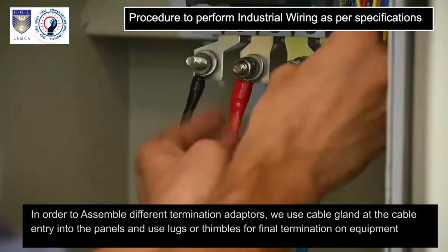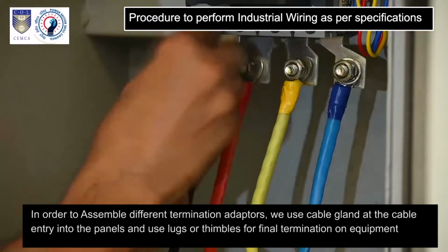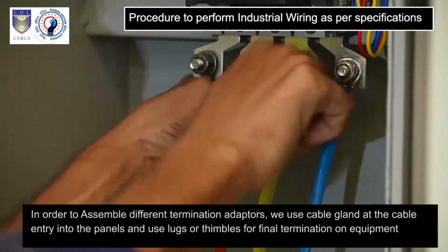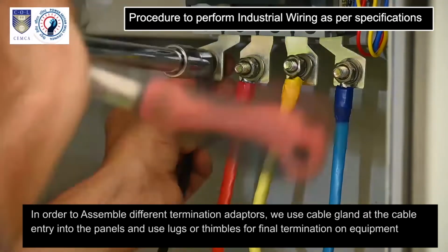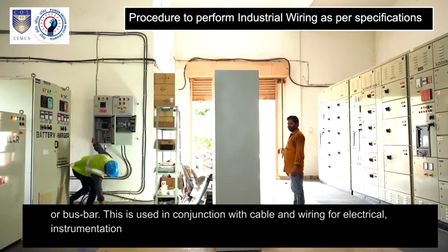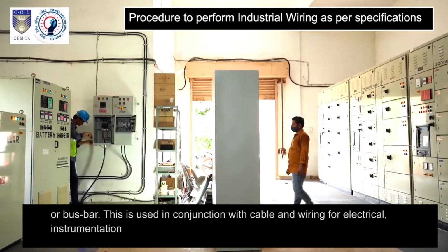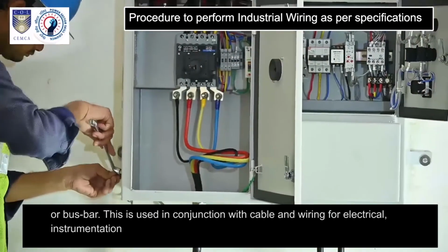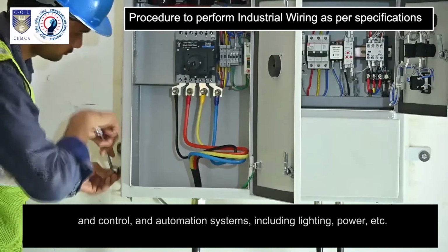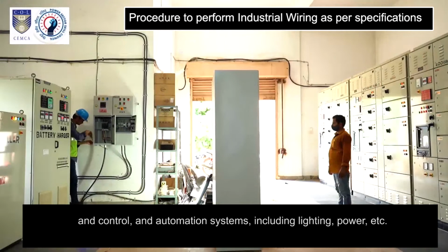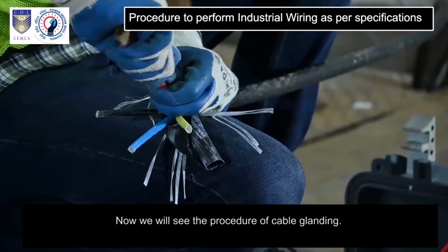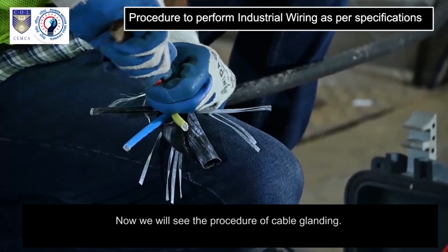In order to assemble different termination adapters, we use cable gland at the cable entry into the panels and use lugs or thimbles for final termination on equipment or bus bar. This is used in conjunction with cable and wiring for electrical, instrumentation and control, and automation systems, including lighting, power, etc. Now we will see the procedure of cable glanding.